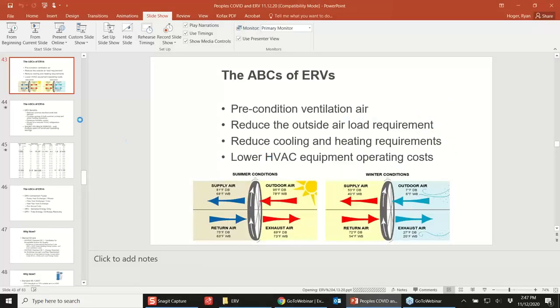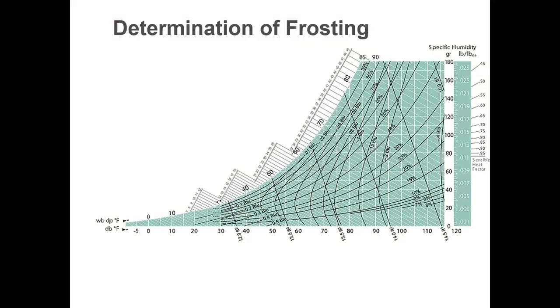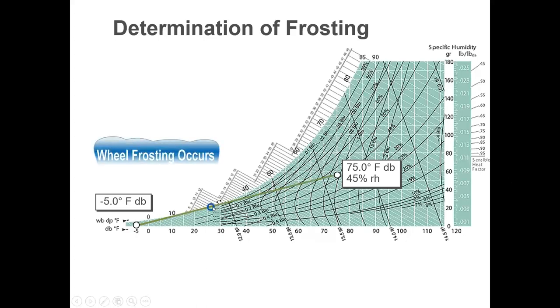So let me go to a much longer 2-hour ERV presentation and just pull up that one slide. Frosting. And what's the fastest way for me to find frosting? There, this one will work. All right, so on a psychrometric chart, what I would do is I would plot my outdoor condition, in this case, a -5 degree day. I plot my indoor return air condition, 75 degrees at 45% RH in this case. And then I draw a straight line between those two things. And if and when they cross the saturation line, the 100% humidity curve, that's when condensation will occur. And if that condensation is below 32, it is going to frost and it's going to be a problem.